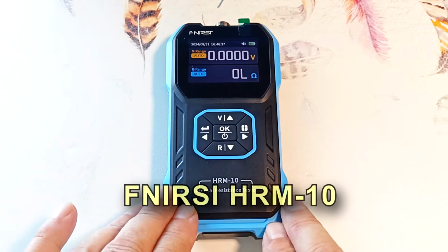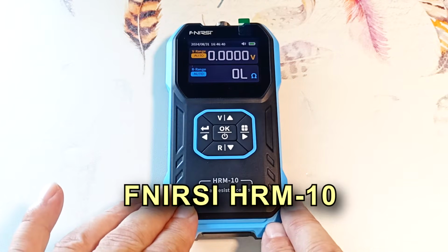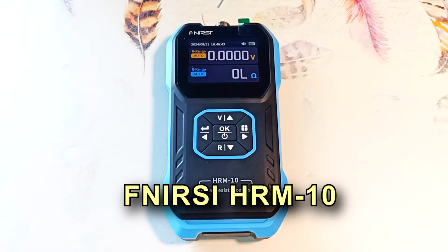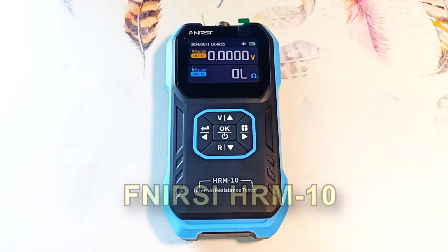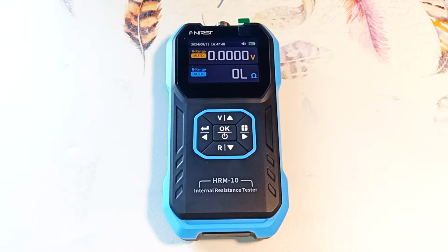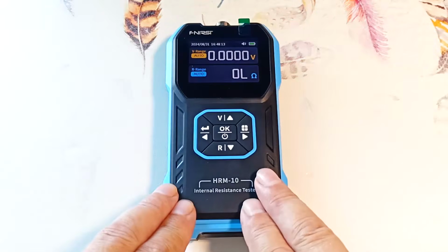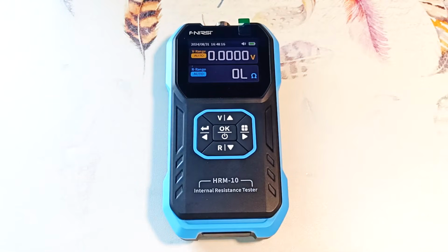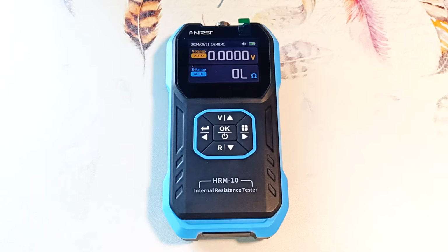Today we will look at the HRM-10 battery internal resistance tester from FNIRSI. But its capabilities are not limited to this. It can measure not only the internal resistance of a battery, but also regular resistance from 1/100th of a milliohm to 200 ohms, and constant voltage up to 100 volts with an accuracy of 0.5%. It can test almost all types of batteries, check the quality of connections and contacts in switches, and determine the real resistance of wires, even short ones. The same device can also sort batteries according to specified parameters. I'll talk about this further in the video.